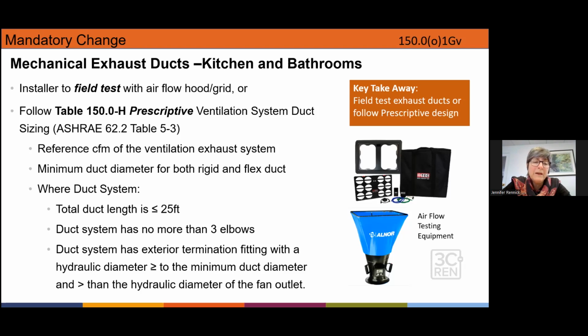For architects, this is maybe a good thing to look at when you're laying out your kitchen, especially if quarters are tight or the kitchen is internal to the house. How are you going to run that ductwork from the exhaust hood to the outdoors? This will come into play more for multifamily apartment projects, where it can be a big deal to keep total duct length below 25 feet with no more than 3 elbows, and there are other requirements as well.